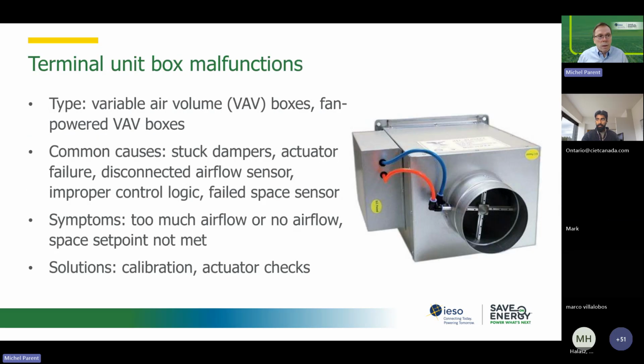If you've got terminal units, that is a bit, I won't say a nightmare, but you may end up with 200, 400, 1,000 VAV boxes in large buildings, and those VAV boxes will have failures. It is very difficult to have a PM program that will go box by box unless you've got a big team. So in practice, what you have to be aware of is how to diagnose failure of VAV boxes.